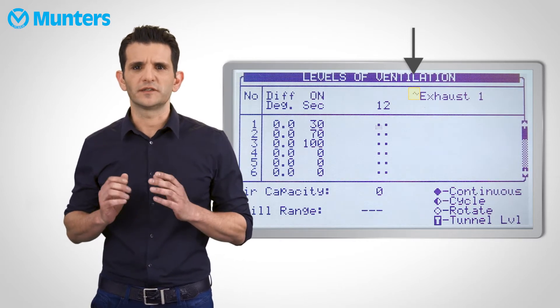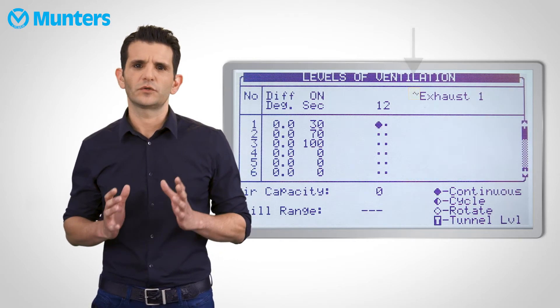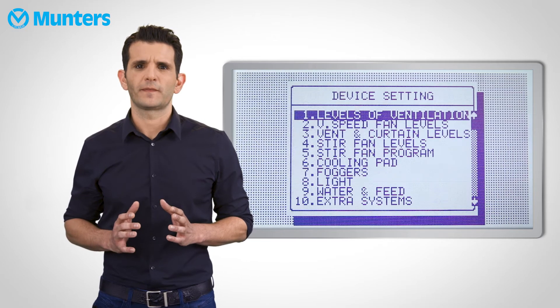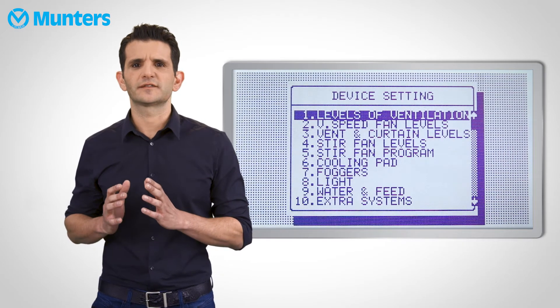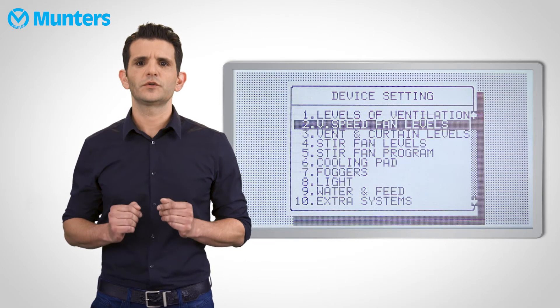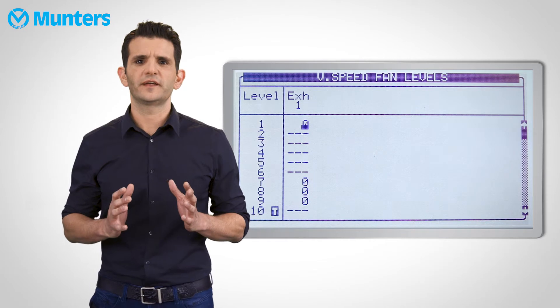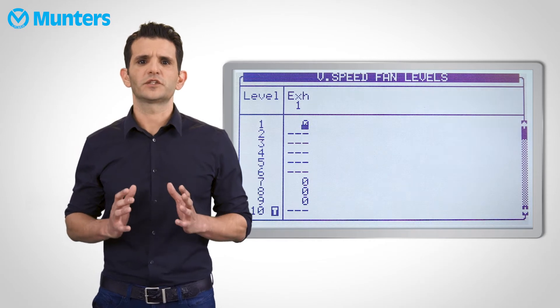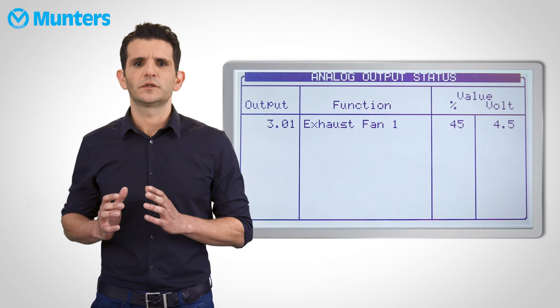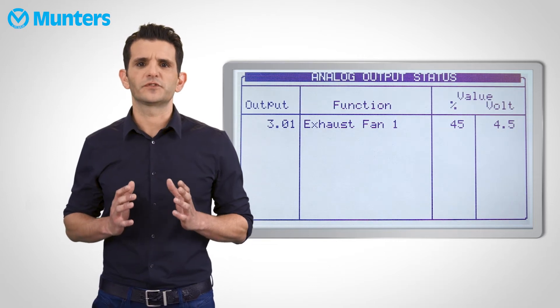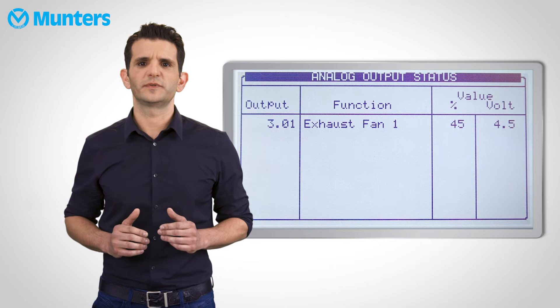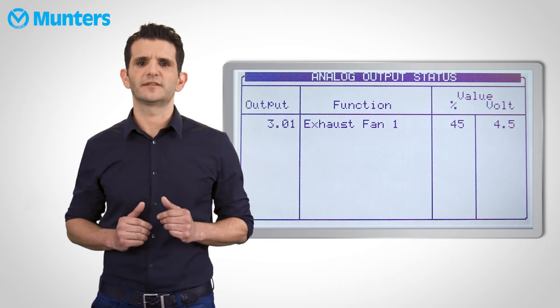This means that this fan is a variable speed fan. You can choose this fan to be continuous or a cycle. Now press Menu to exit this table and select the second table, Variable Speed Fan Levels. Here you can select the speed of the fan for each level. Pressing 7 on the main screen will take you to the Analog Output screen, where you can view all the variable speed devices with their current intensity.